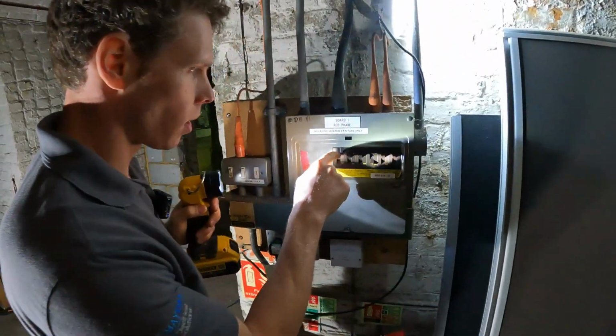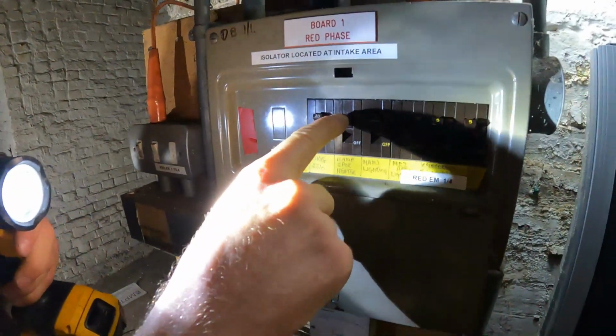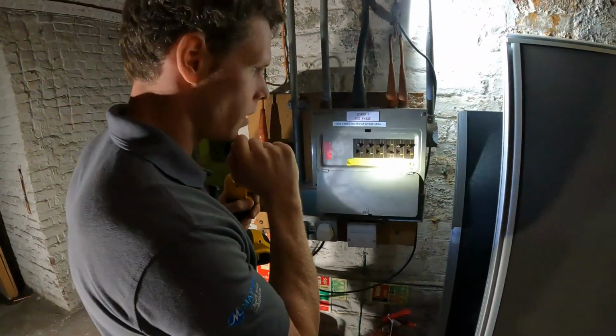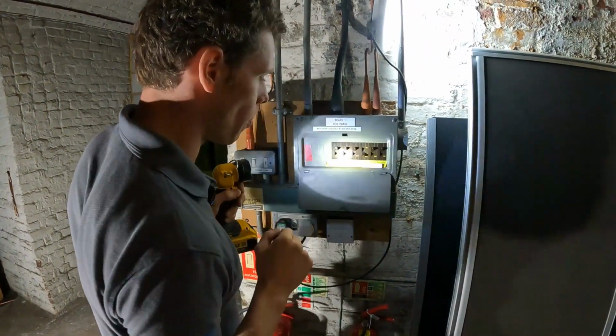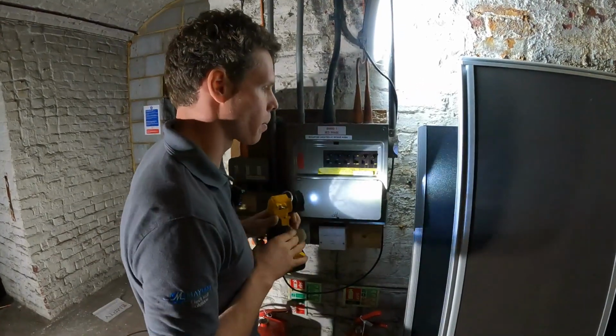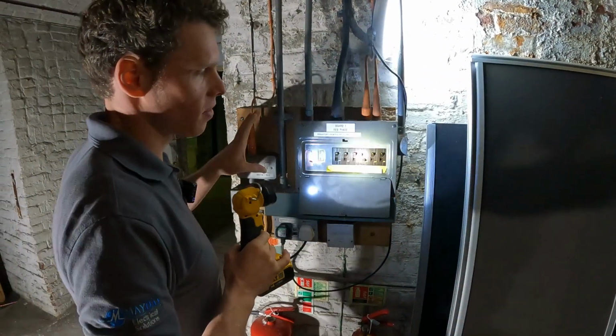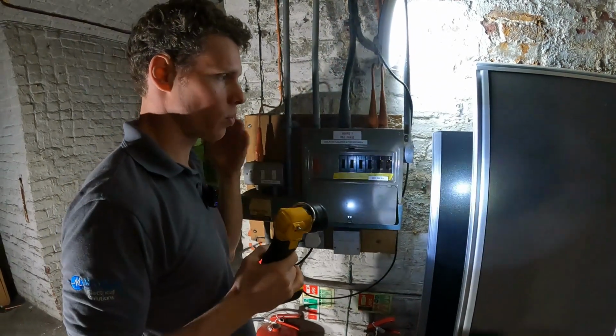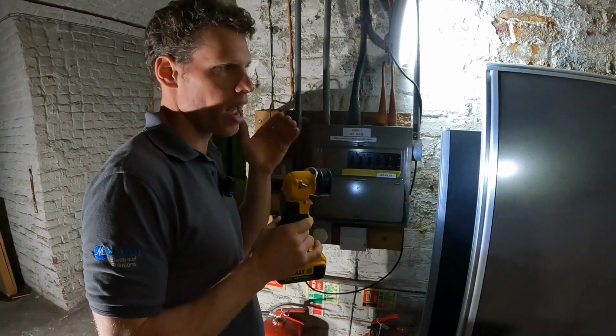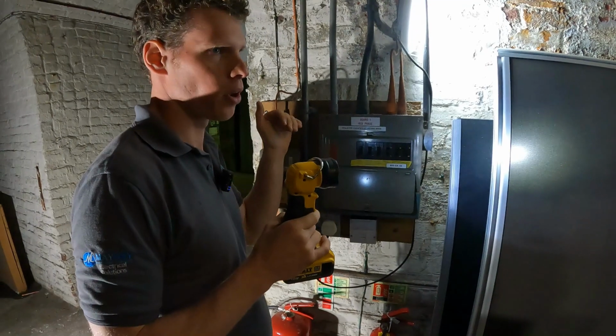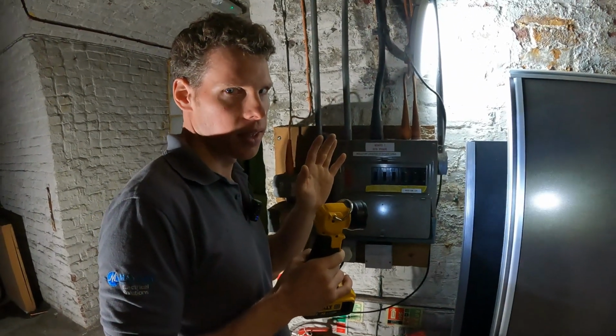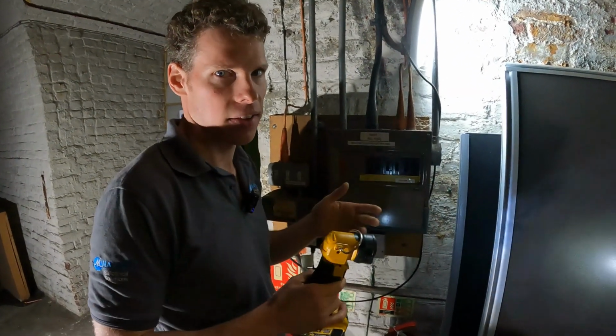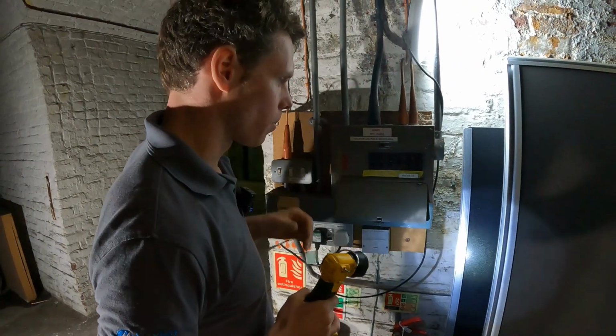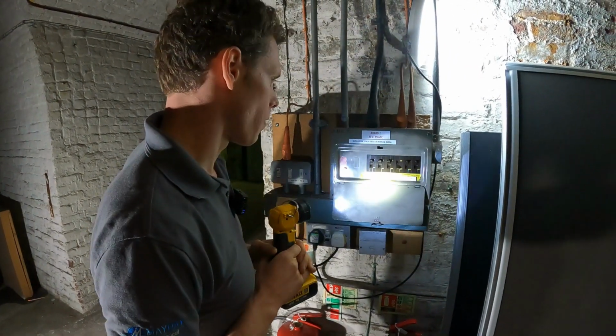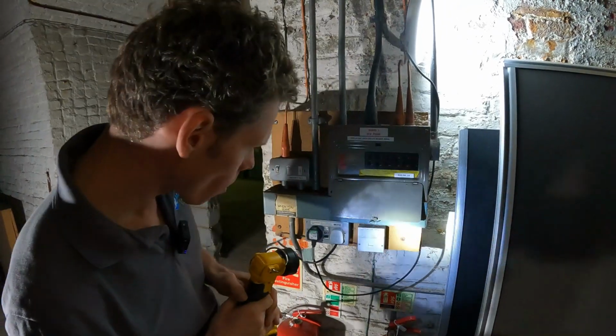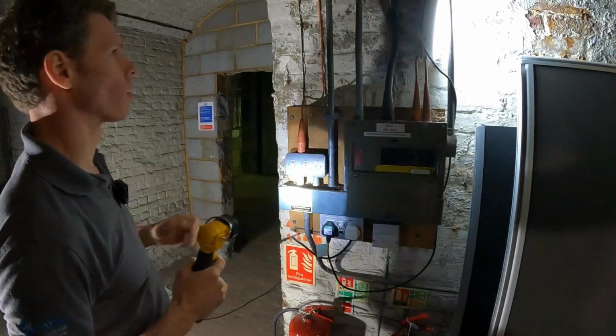Correct me if I'm wrong, I think the yellow tab is 4.5 kA - the amount of current it can take before it blows. What we often find is that because a lot of these are commercial, they tend to be attached to submains, so you rarely get a fault current at this position above 3K. Because by the time you factor in your Zs, you end up with a compliant kA rating.